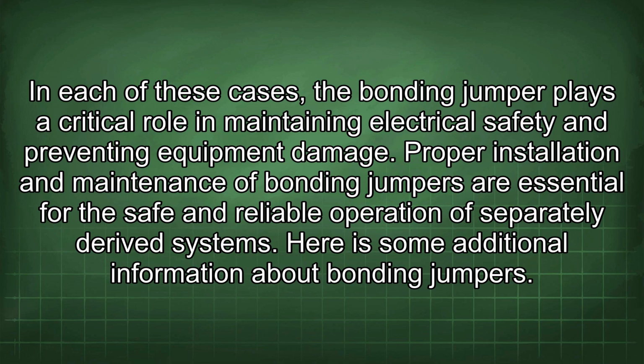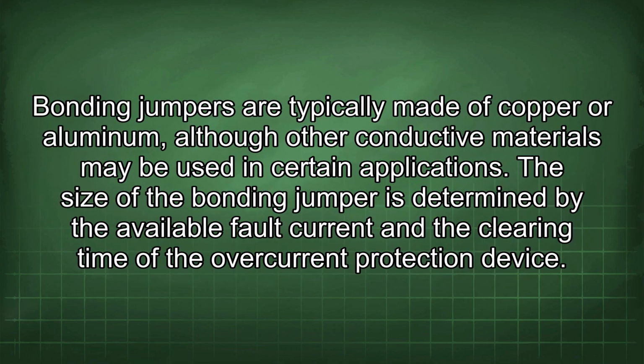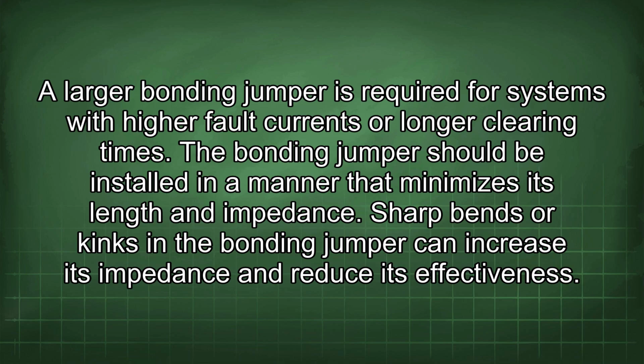Here is some additional information about bonding jumpers. Bonding jumpers are typically made of copper or aluminum, although other conductive materials may be used in certain applications. The size of the bonding jumper is determined by the available fault current and the clearing time of the overcurrent protection device. A larger bonding jumper is required for systems with higher fault currents or longer clearing times. The bonding jumper should be installed in a manner that minimizes its length and impedance. Sharp bends or kinks in the bonding jumper can increase its impedance and reduce its effectiveness.